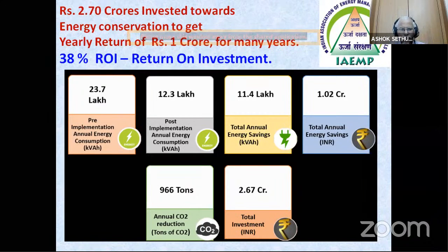So for 2.7 crores of investment in the Niti Aayog buildings, 1 crore was the return per year, almost 40%. Consumption was almost 24 lakh units before and almost 12 lakh units after, so almost 50% of the consumption was saved.